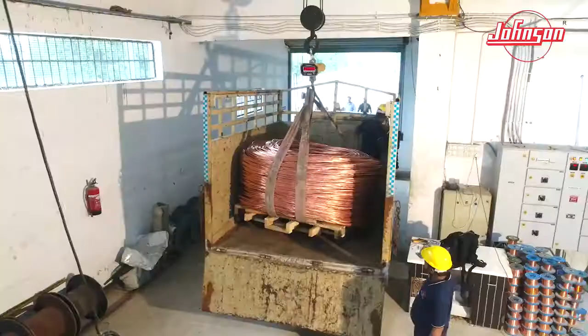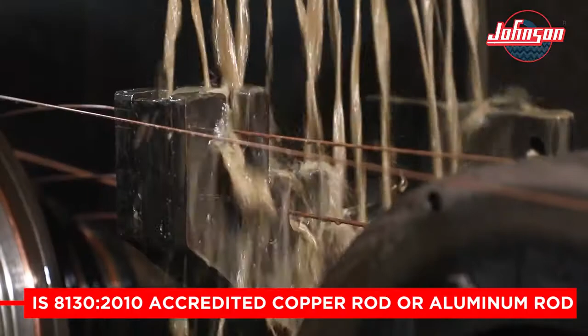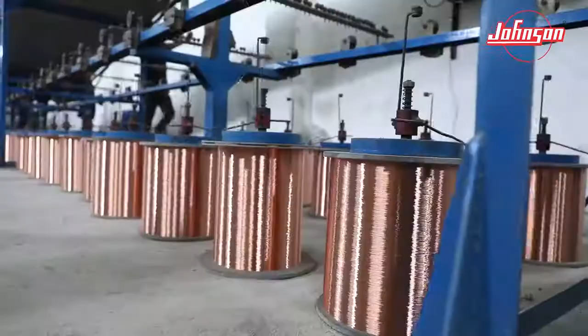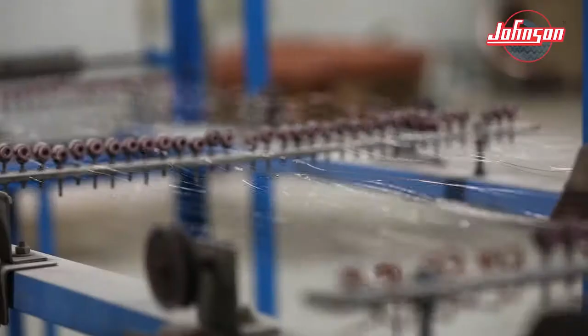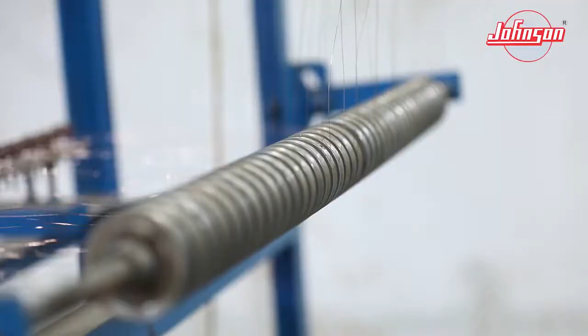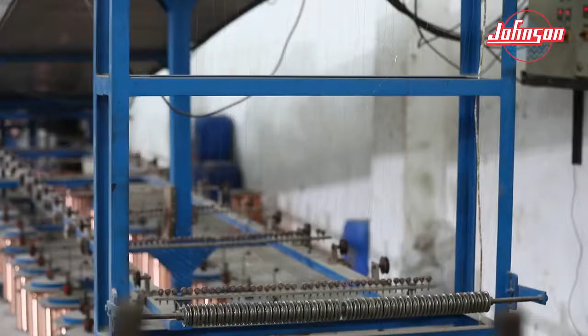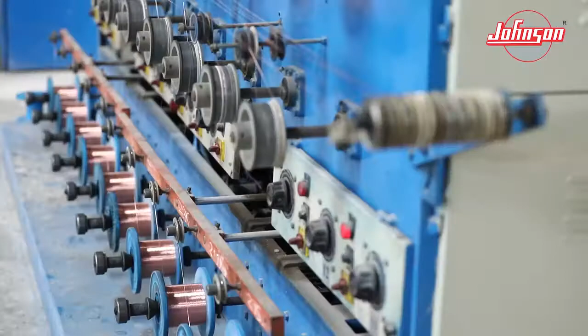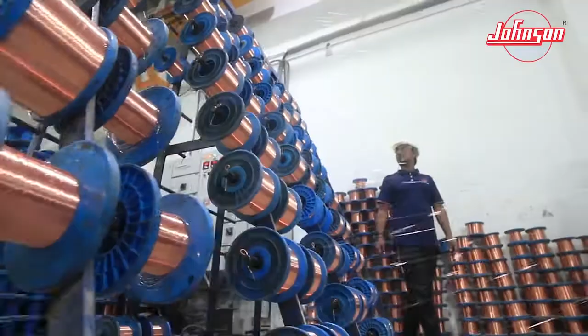At Johnson Cables, the cable manufacturing begins with the wire drawing of the IS 8130-2010 accredited copper rod or aluminium rod, wherein the diameter of the rod is drawn out to the required size with the help of the wire drawing machine and passed through the annealing process to raise the ductility and conductivity to the greatest extent.